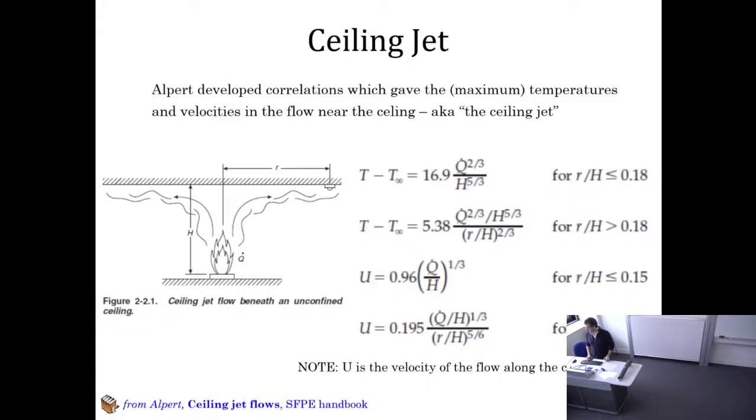Okay? There is a theory, a beautiful theory, that tells you what happens not just to the smoke. There's not a plume. When the plume touches the ceiling and bends laterally, it's become what is called a ceiling jet. It is the same phenomenon, but now has been forced to use that buoyancy and that momentum to go horizontally. It doesn't grow any farther because of height. It just continues horizontally. It's a ceiling jet.